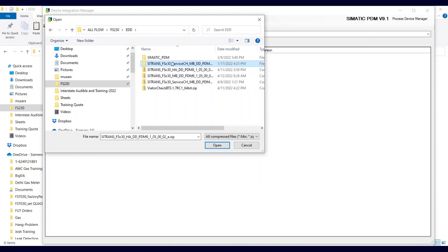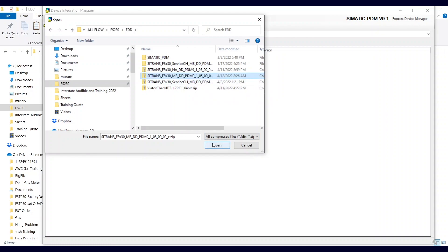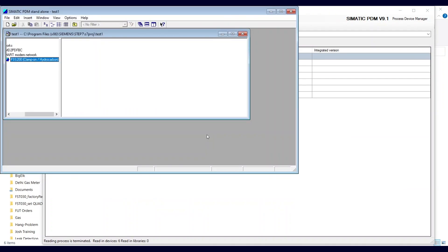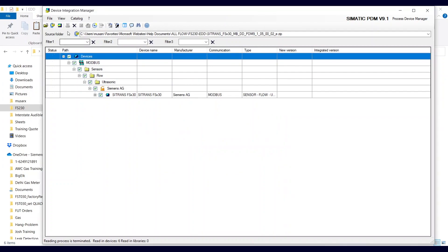I have already loaded the service channel EDD and the one below it, which is HART. So let's do the regular channel 1 input for Modbus. Make sure all devices are checked by clicking on devices, then come up to Integration and click. If you get a message that PDM may already be running in the background, close it and try again. And there it goes — it's done.